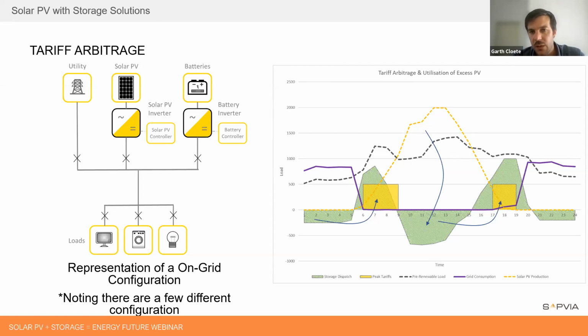In this case, with the mix of solar PV plus battery storage, we've got almost no consumption coming from the utility grid between 6 a.m. and 7 p.m. in the evening. So starting on the left-hand side at midnight, we're slowly charging the battery storage, charging it as slow as possible so as not to create any peaks in the maximum demand. Then as we get into the morning, where the initial peak tariff starts kicking in, we start dispatching that storage - you can see that in the green solid line section - pushing that energy into the grid. At the same time, the solar PV starts generating.